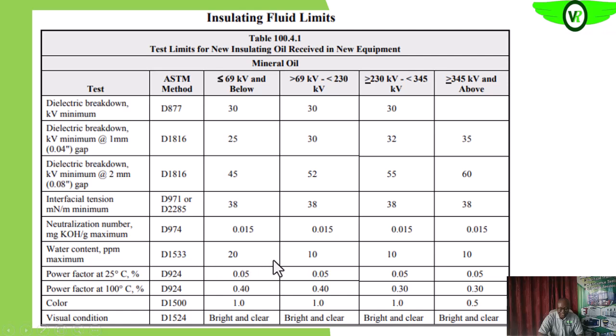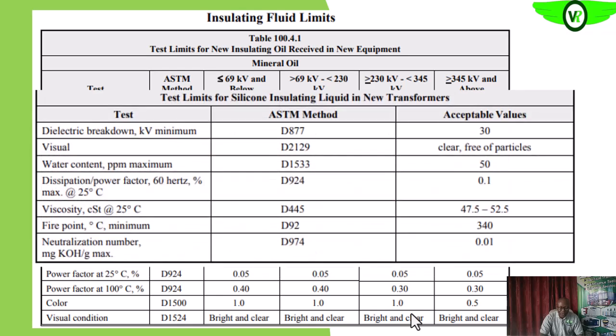Then the water content, these are some of the recommended values for different voltage levels, as you can see. Then the power factor, these are some of the recommended values. Then the color and the condition of the oil. You can use this table as a guide during your inspection and testing of the transformer. So for silicone insulating liquid in new transformers, these are some of the acceptable values for those parameters.